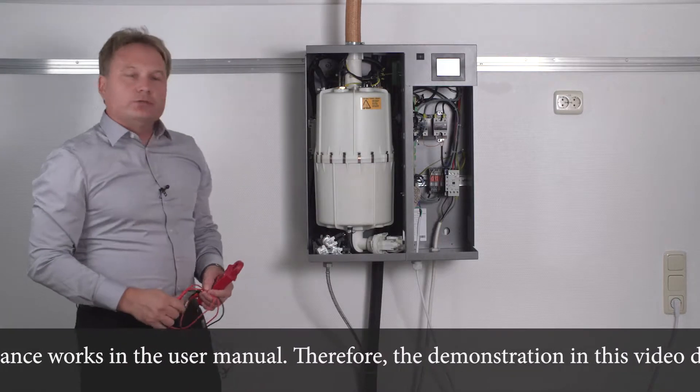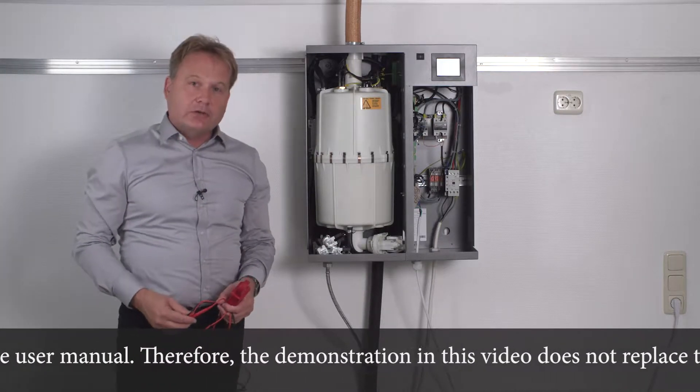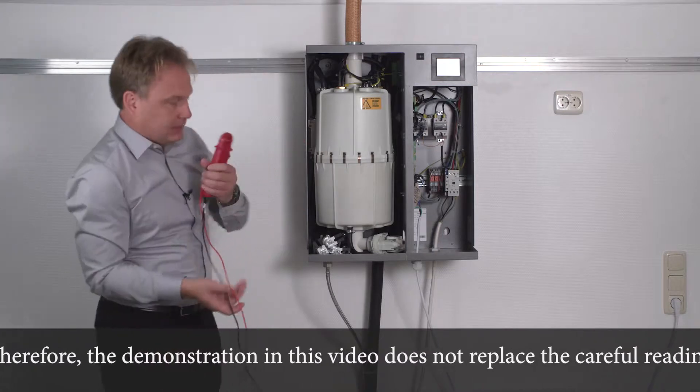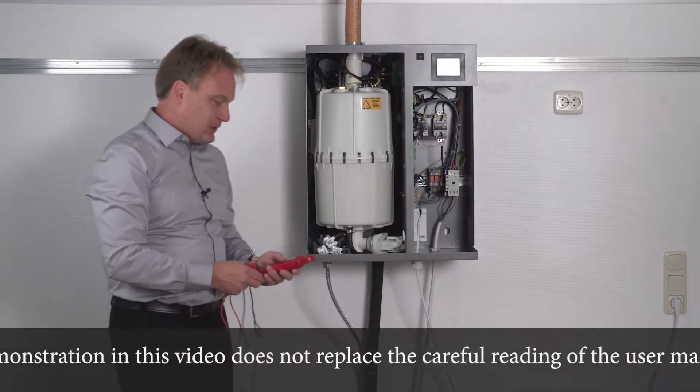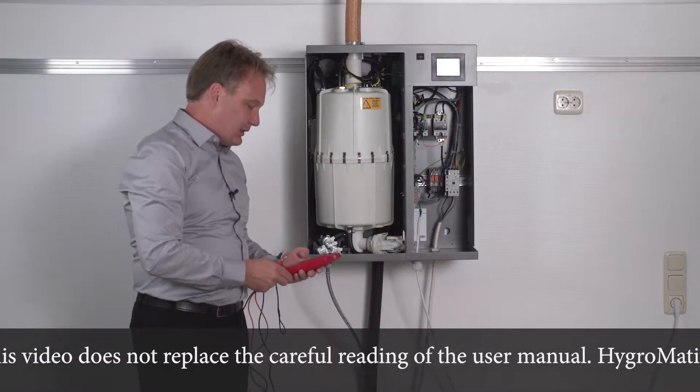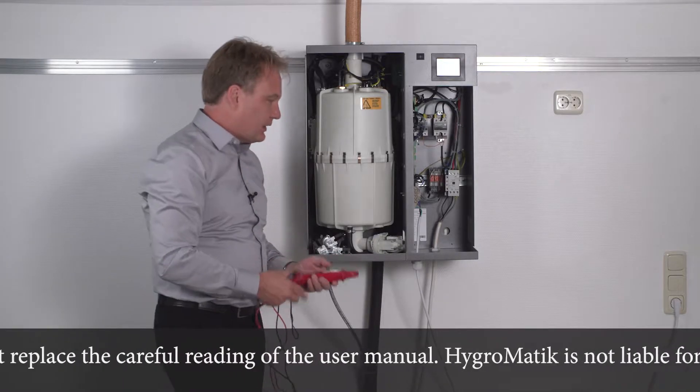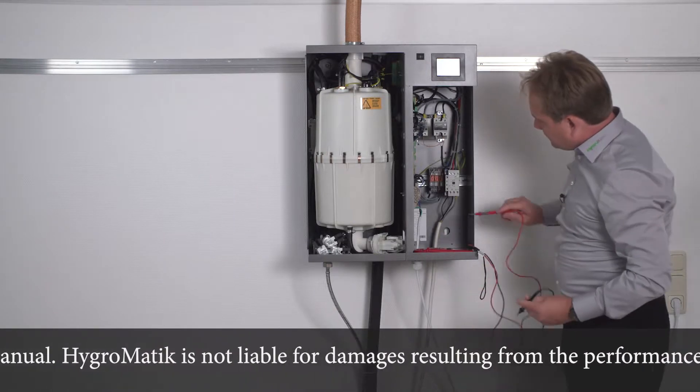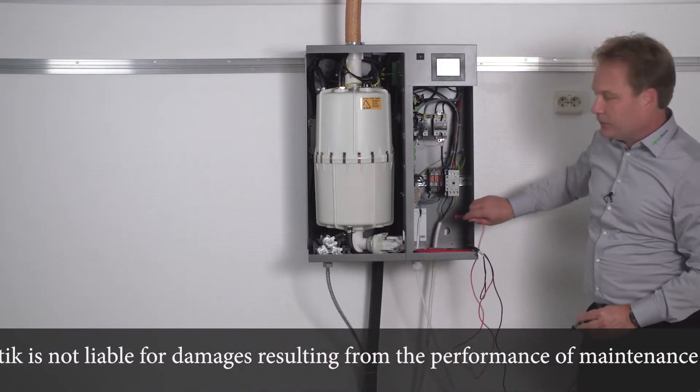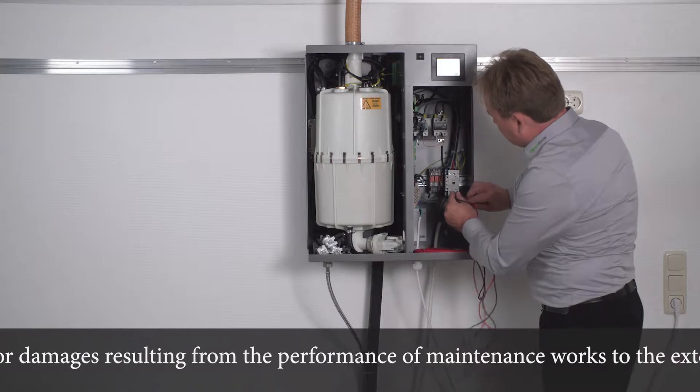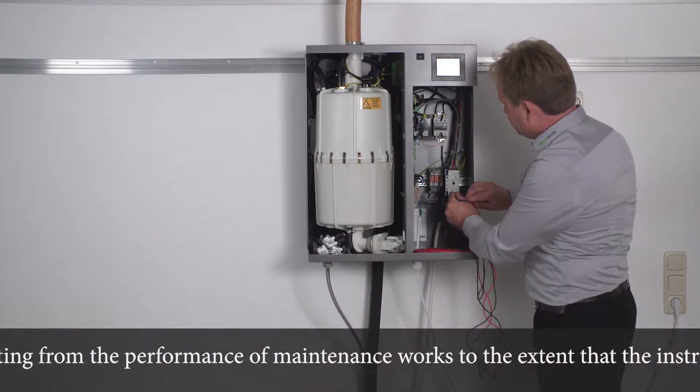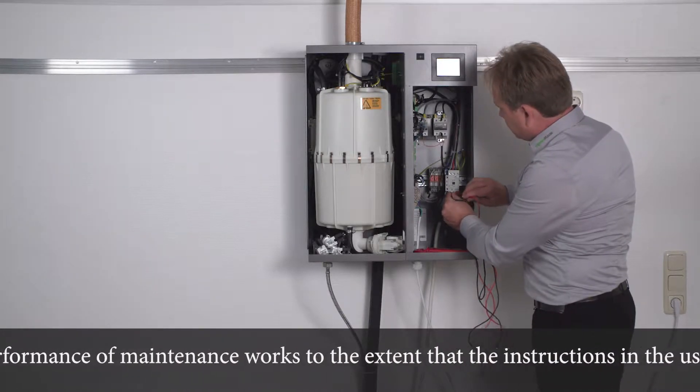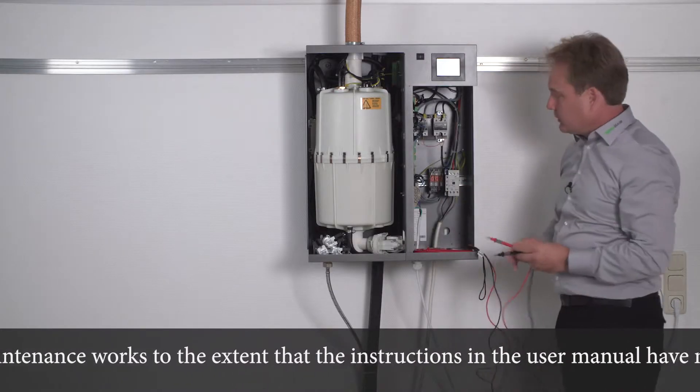After the unit has been opened, I must check that no voltage is present. This is very important. By using a normal voltmeter to verify no voltage is present, I will check the connection cables at the main contactor and check all phases for voltage. There is no voltage here.